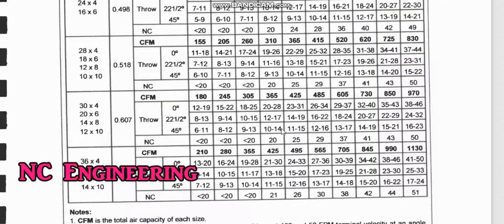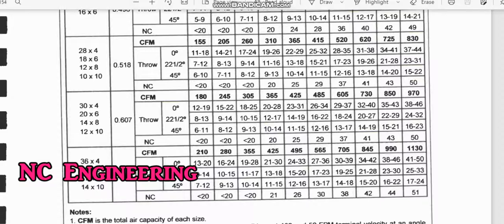If you follow only 600 FPM you can also go for a bigger size: at 425 CFM the velocity will be 600 FPM, the throw is 30, and the NC level is 21. Since we need NC 25, we can select the smaller size. Both sizes are acceptable. Let us now go for the linear slot diffuser.